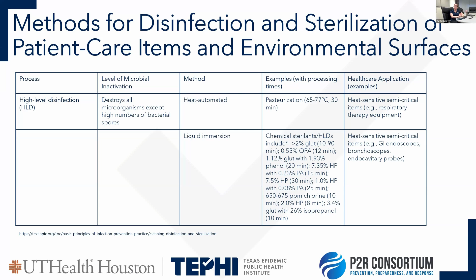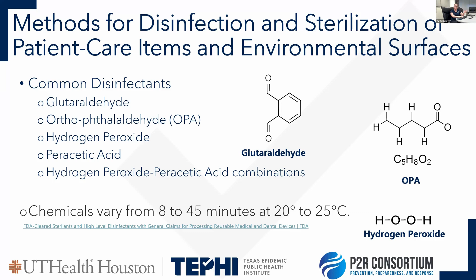Some common disinfectants that we use in this process are, you can see here, our OPAs and our hydrogen peroxide. I want you to pay attention that bleach is not one of these chemicals. So if you're auditing or monitoring something and you're looking at the device and it says high-level disinfection, that does not mean cleaning it with bleach, which does not properly disinfect all the material. So it needs to be a specific chemical. Some common ones are listed here, and the time and temperature variation is dependent on that piece of equipment and that chemical composition. So different chemicals will have different times. It's not a one size fits all type of thing. And based on your piece of equipment as well, you'll use different temperatures of disinfection and times for those cycles.